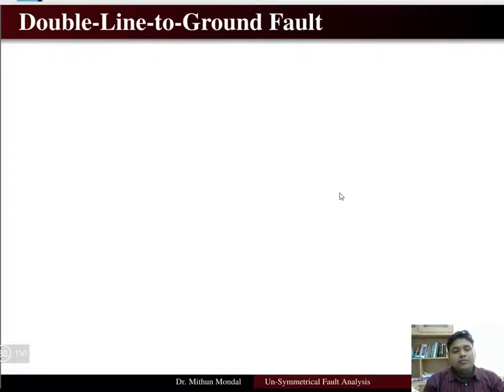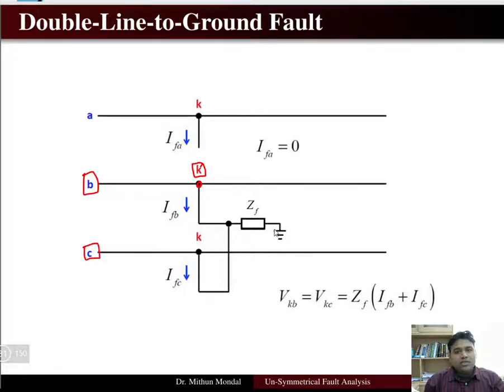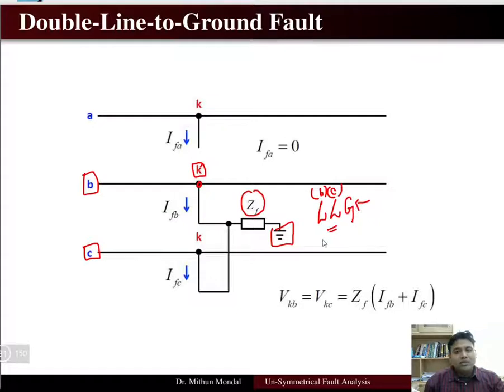Welcome to lecture 44 of Electric Power Systems. In unsymmetrical fault analysis, we are going to discuss the double line-to-ground fault. Here we can see that there is a fault occurring at bus number k in phases b and c. The line-to-line fault is associated with a fault impedance Zf, and such a fault is known as a double line-to-ground fault because two lines and a ground are associated with the fault.